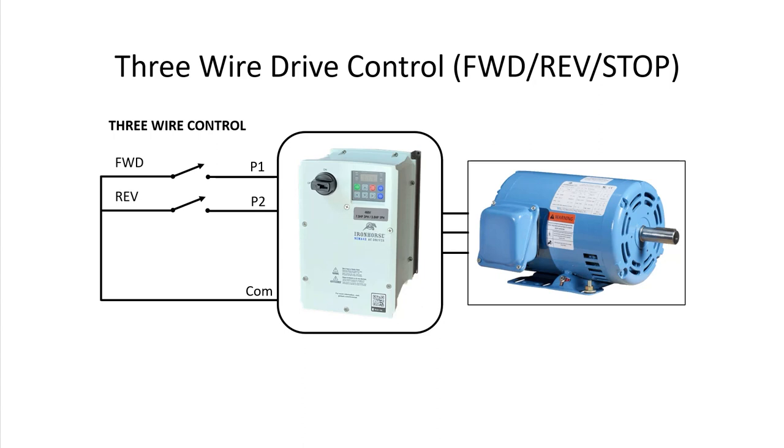To change to 3-wire control, just swap the selector switches with momentary switches and add a third normally closed momentary switch for stop control. We'll use input terminal P3 for that.